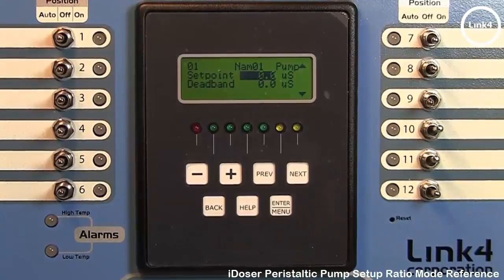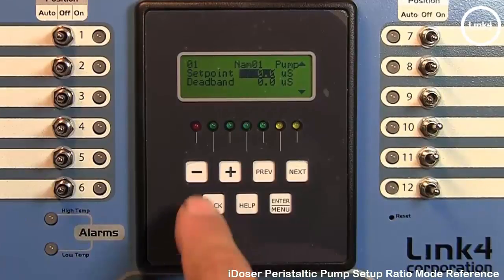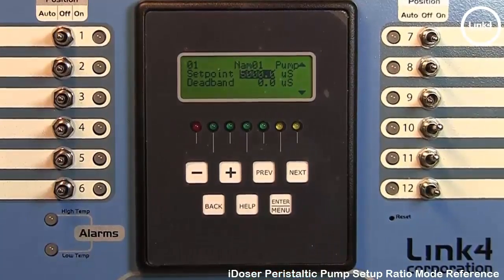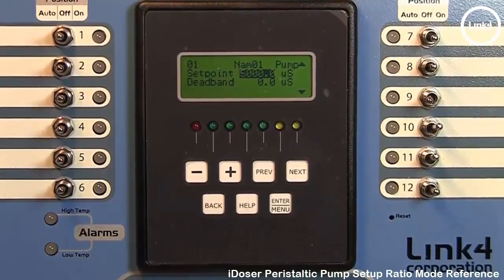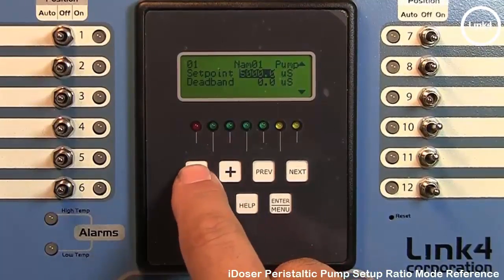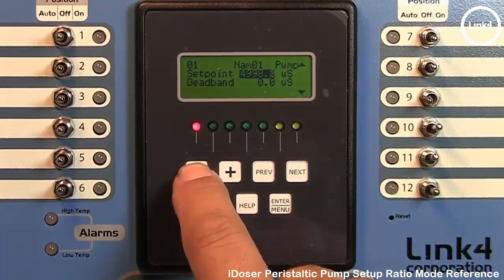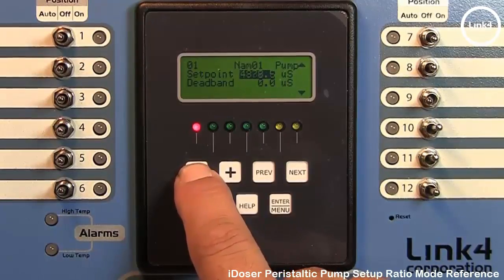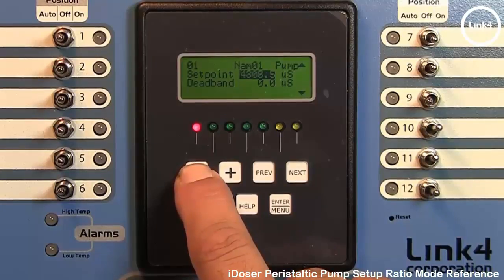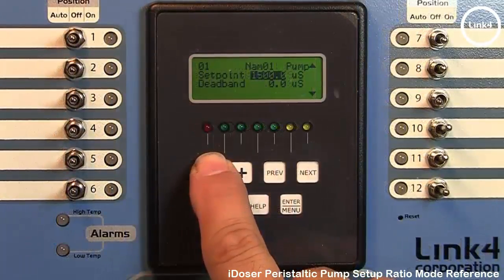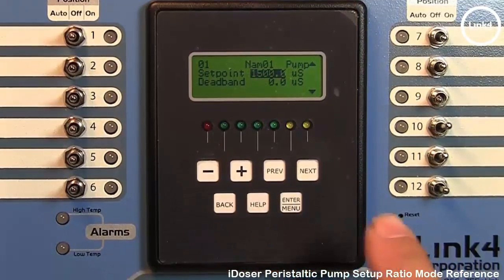Now in this screen we have set point. Now the EC probe set point can be up to 5,000 microsiemens. Hitting next gets us to that 5,000 value. You would use plus and minus to determine what values you want to input for your set point. And you also have the option to set a dead band as well. But what we're going to do is leave this at about 1,500 microsiemens. And we'll leave it at 1,500. Hit next.